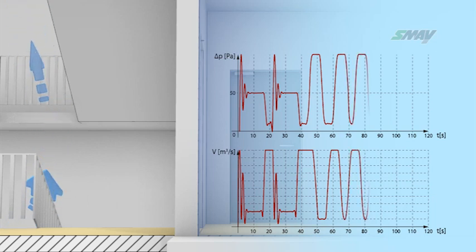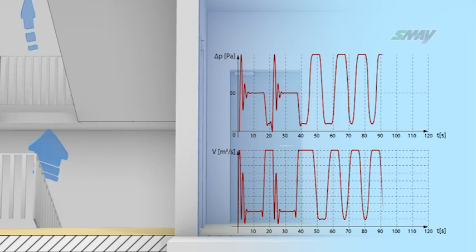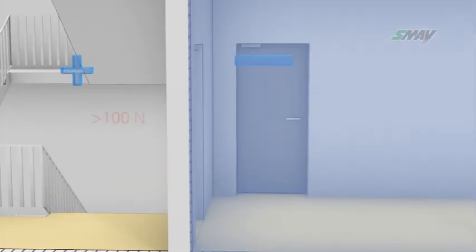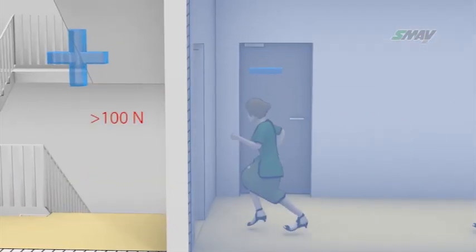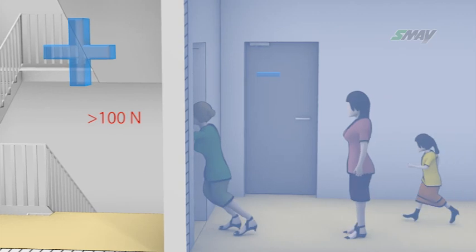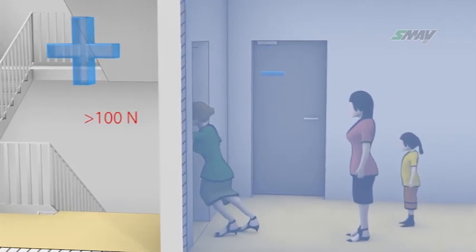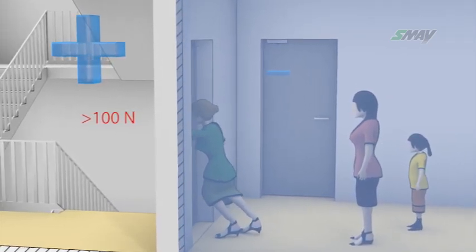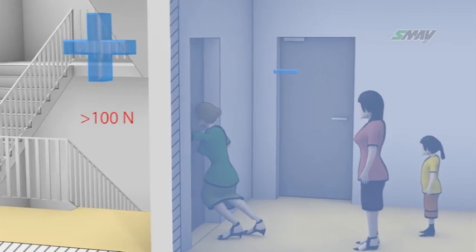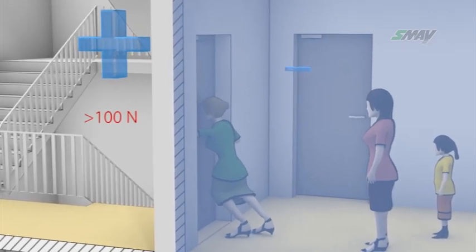For example, the oscillatory increase of pressure to 150 Pa will increase the required door opening force to 200 N, which will hinder its opening. The force necessary to open the door exceeds the allowed level of 100 N, which may last from 10 to 20 seconds. The staircase will be cut off from the evacuating people.